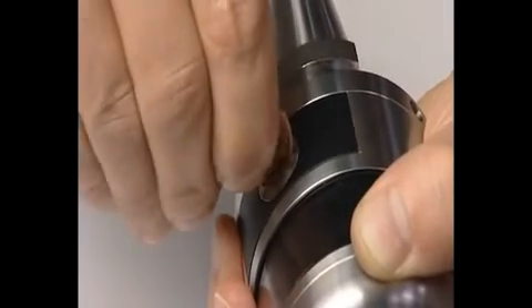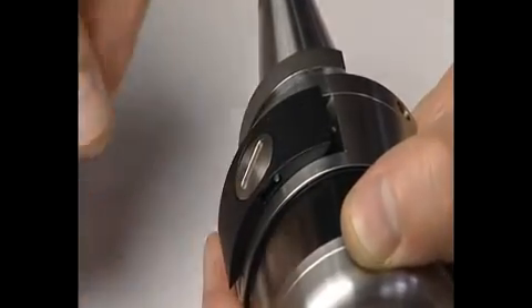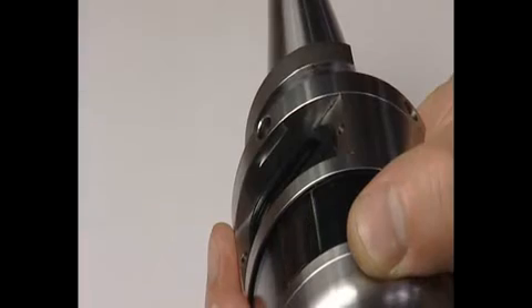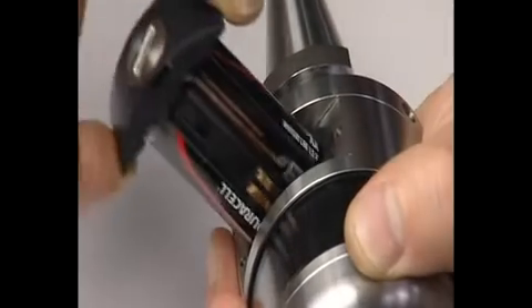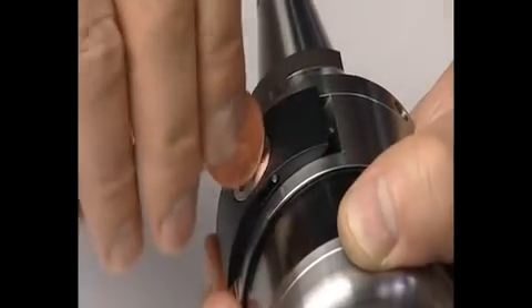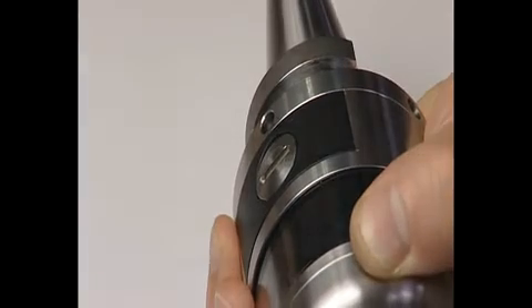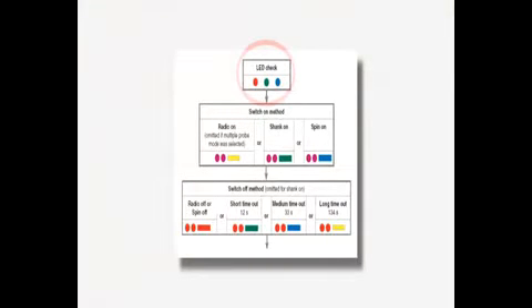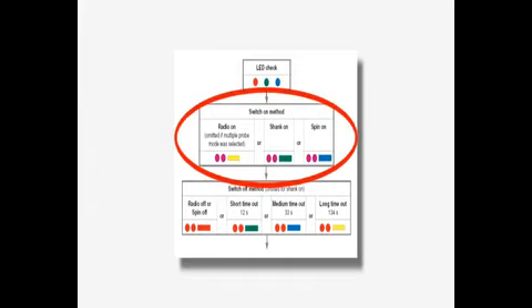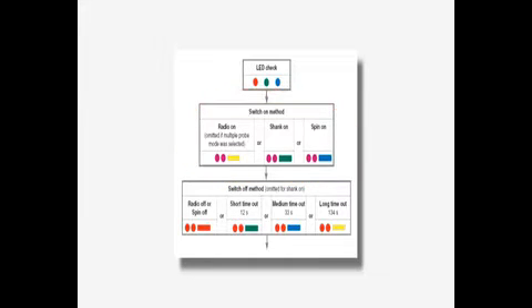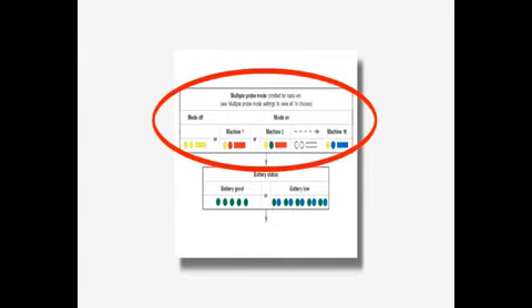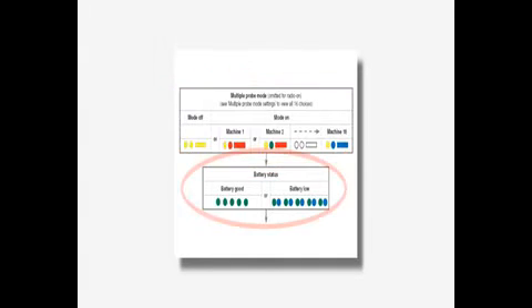To review the current probe settings, remove the battery cassette for 5 seconds. Then reinsert it. When reviewing settings, do not deflect the stylus. The probe now goes through a startup sequence: an LED check, the switch on setting, the switch off setting, multiple probe mode, and a battery status review. The probe will return to its standby mode after 10 seconds.